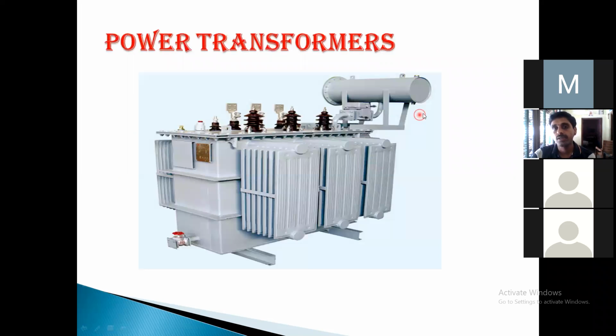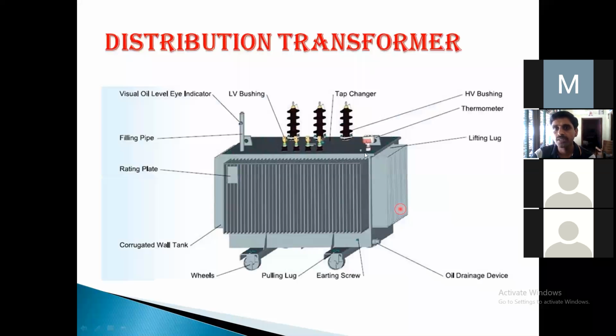So this is a simple power transformer picture. You can see. So this is the distribution transformer. High voltage bushings are there. These are low voltage bushings and a filling pipe, oil filling pipe, and rating plate here. And this is a wall tank, wheels to move this one. And this is the oil drainage device to remove the oil, because oil is a very important part here for cooling purpose. The lifting lug, high voltage bushings. These bushings you can see outside. The thermometer to measure the temperature of the oil.